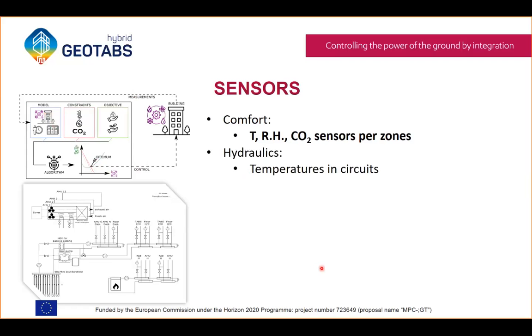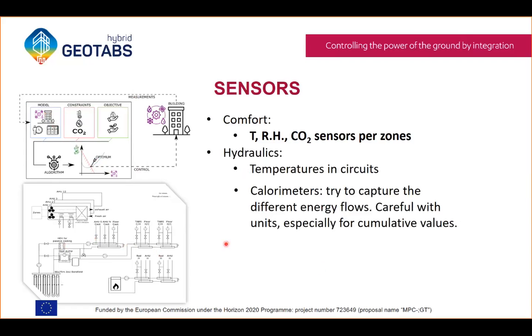For the hydraulics, it's of course important to have several temperature sensors within the circuits to check the system, but this is mostly something the installer needs too, to make sure the system works properly. Besides that, it's interesting to install a few calorimeters just to know the different energy flows—for example, one for the taps, one for the radiators, one for the ventilation. That gives a feeling for where most of the energy is going, and helps find mistakes in the system or know what should be optimized first. But the problem is that in most buildings I've seen, the calorimeters were either not properly installed or not properly connected to the BMS system, so they're not so reliable, unfortunately, and I'm not sure exactly why.